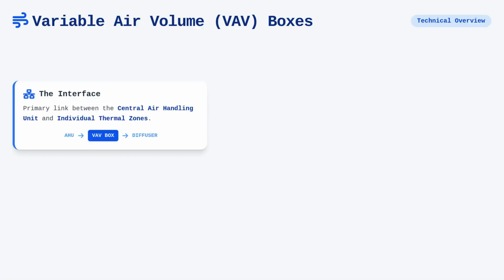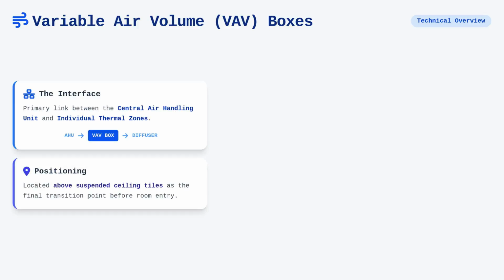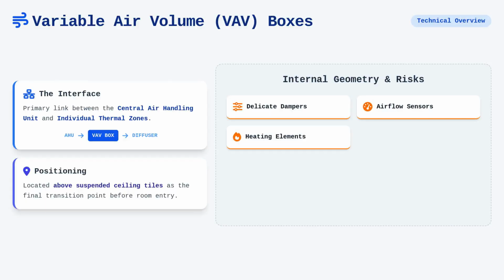Variable air volume, or VAV, boxes serve as the primary interface between the central air handling unit and the individual thermal zones of a building. These units modulate the volume of supply air based on the specific cooling or heating demand of a zone, which is why understanding their internal geometry is crucial for any cleaning specialist. You will typically encounter these devices above suspended ceiling tiles, positioned as the final transition point before the air enters the room through diffusers. The complexity here lies in the compact design, which often houses delicate dampers, airflow sensors, and heating elements within a very confined steel casing.